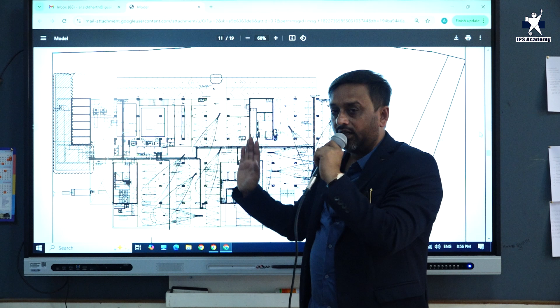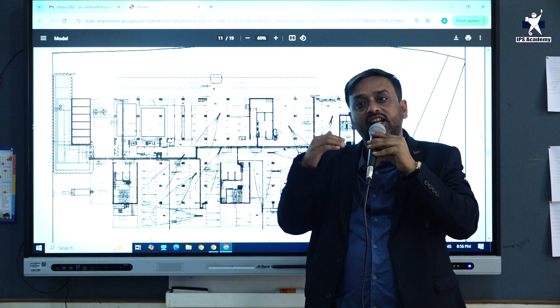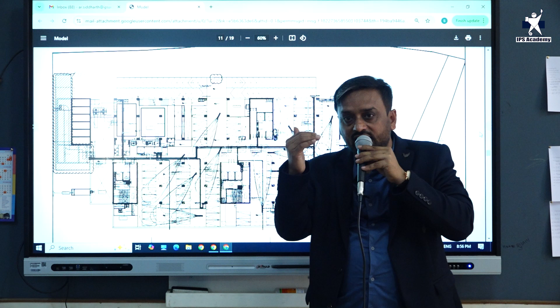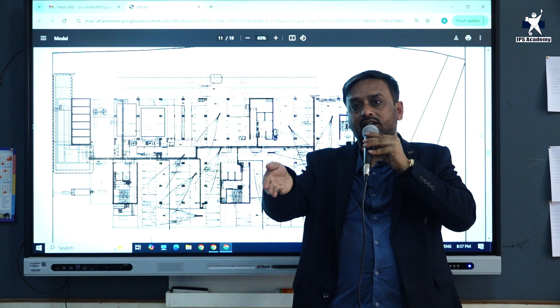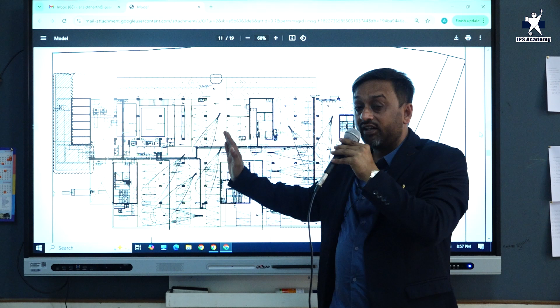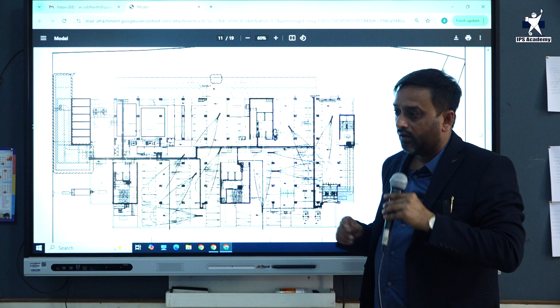In any mechanism in India or anywhere in the globe, we cannot throw all the air from one end to another end. So it is very much important to create 2 zones to have the efficient air exhaust or supply. So there is a limitation. See, why we are using jet air fans? To save our height. If we are moving in a direction that we should use 1 zone, you need jet air fans in the size of 1200 mm. Presently these are of 400 mm. So again, you will be in the same situation. So we were avoiding the ducts, and now we are having the higher dia of jet air fans, so it won't make sense. So to control the airflow efficiently, we are making zones. If it is 67 or 70,000 square foot, there would have 3 zones also.